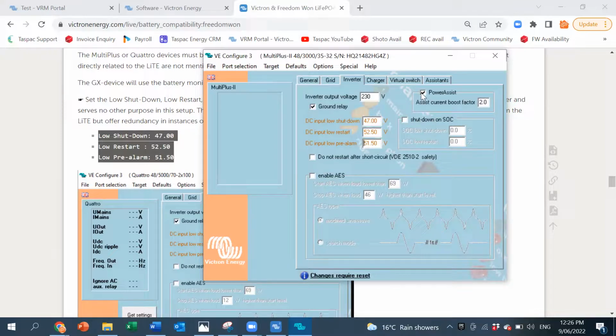Power assist, again, if the generator is say 10 amps and you have a load of 20 amps, the inverter will boost the generator. But if you untick that, the generator will try and take the whole lot, and it will probably kick the generator out or overload it.